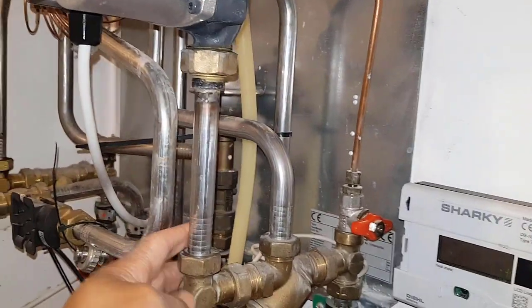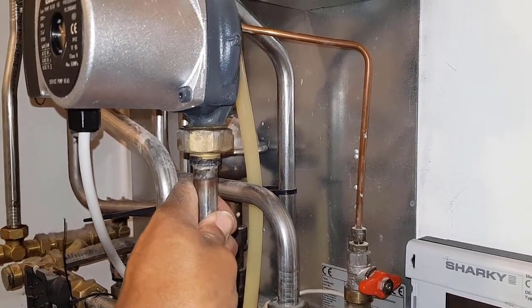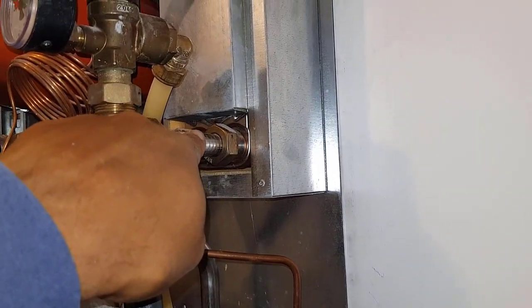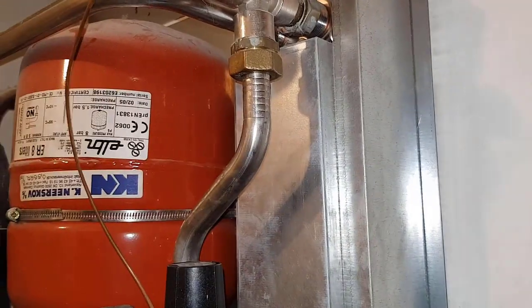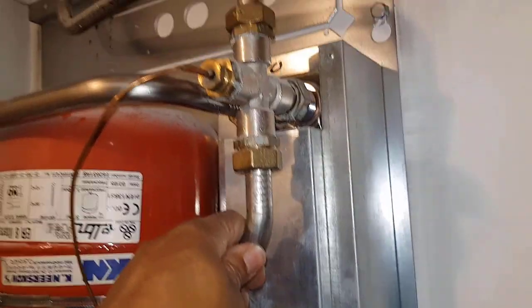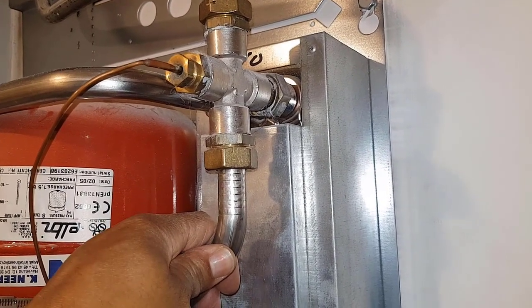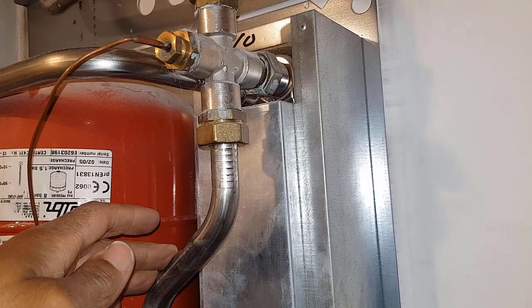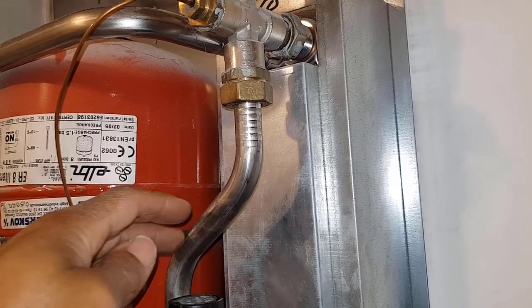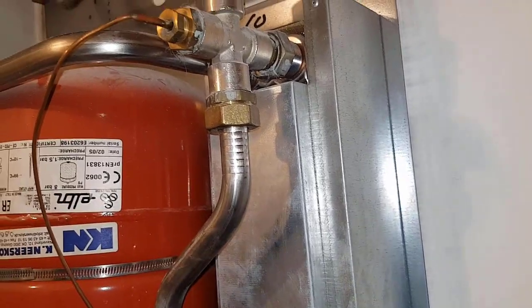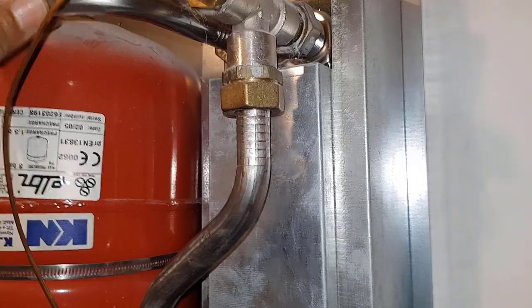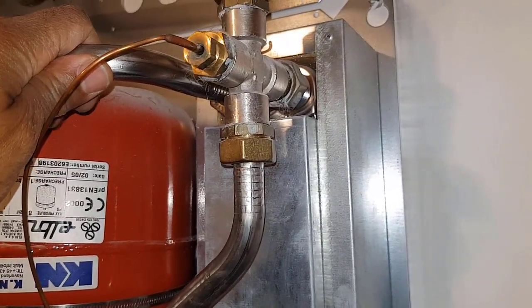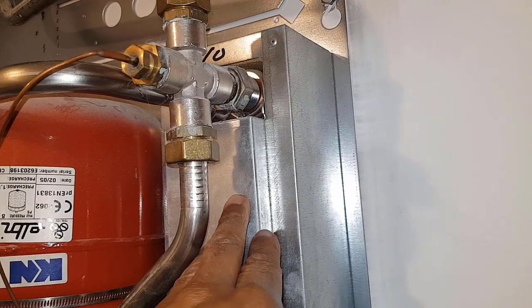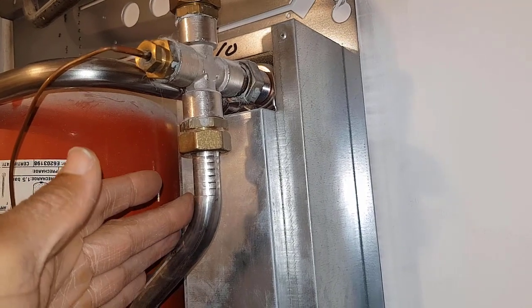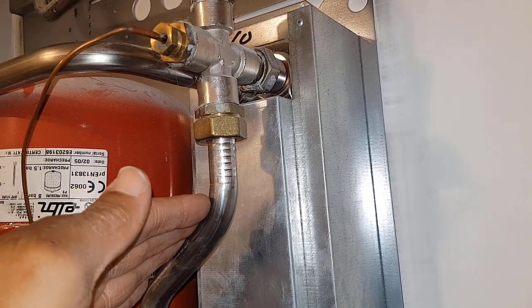So what should happen, as I said, is the return should be sucked up in here. That's cool water. Pump it into the plate, and then this is the flow, which should be getting hot. However, this is not getting hot. So we've got some sort of restriction, because this is the main flow going to the radiators, but it's still cool. What should have happened is the main flow which comes across here, which is quite hot, should mix, heat exchange should take place, and then we're getting heat transferred into this flow pipe going to the radiators.